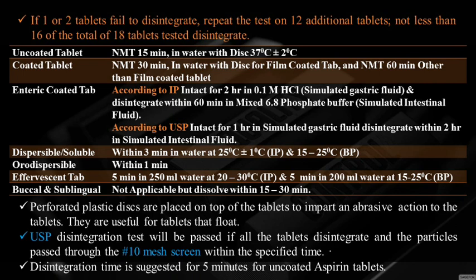Some important points: perforated plastic discs are placed on top of the tablets to impart an abrasive action and are useful for tablets that float. The USP disintegration test passes if all tablets disintegrate and particles pass through a 10-mesh screen within the specified time. Disintegration time suggested for uncoated aspirin tablets is 5 minutes, whereas for general uncoated tablets, not more than 15 minutes.